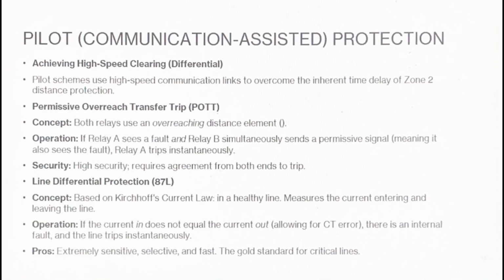Last slide is about pilot, communication-assisted protection. This is where protection gets its speed advantage. Pilot schemes eliminate the time delays associated with zone 2 of distance protection by using a communication link. POTT, permissive overreach transfer trip. This uses a distance element that overreaches the line. If relay A sees the fault, it doesn't trip immediately. It waits for a permissive signal from relay B. If relay B also sees the fault, they both trip instantly. This uses agreement to ensure high security.